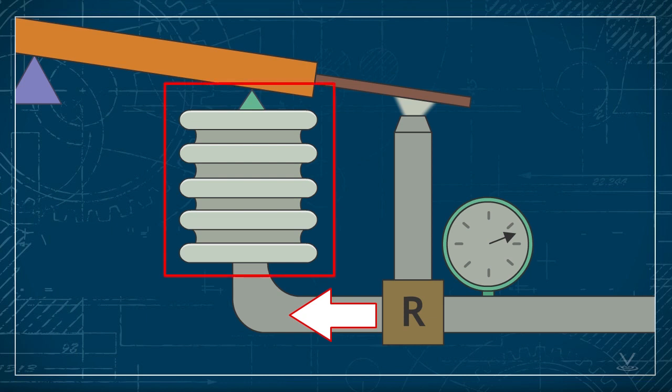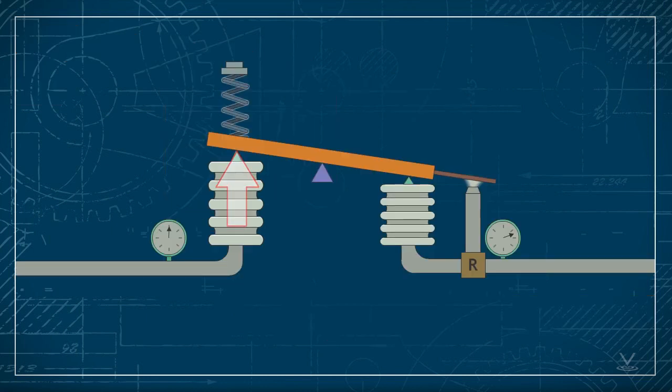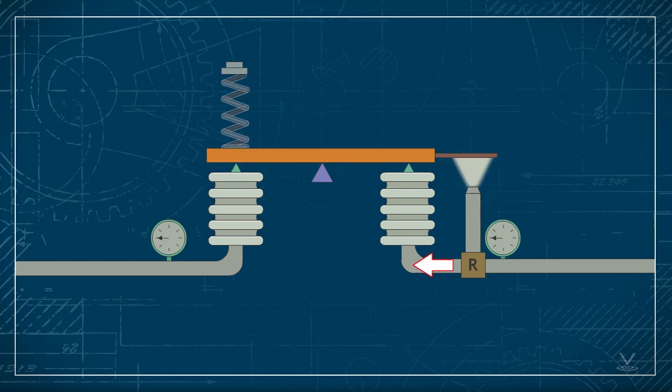For one, it's fed to the output balancing mechanism, another bellows, which we'll call a feedback bellows. If input changes, the new output causes the feedback bellows to bring the controller back into balance.